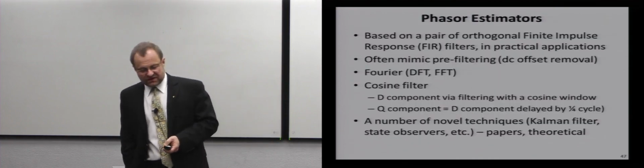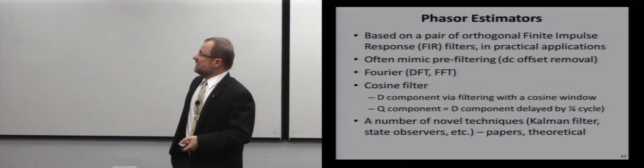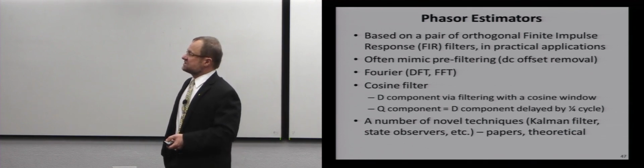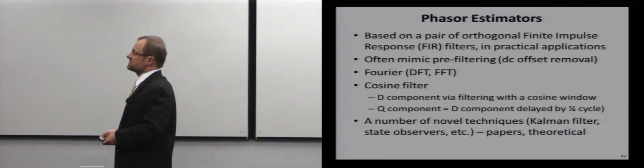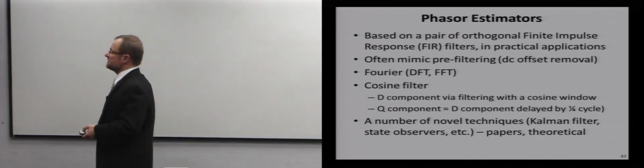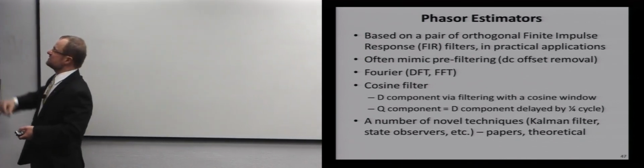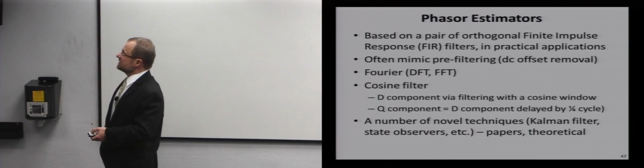So to summarize phasor estimation, typically what we have is we just use a pair of orthogonal filters. Sometimes we need the explicit removal of the DC offset. Many relays use Fourier.